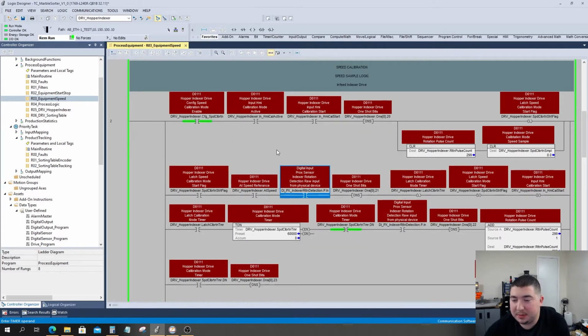So the next thing we want to do is our speed sample. In order to do that, we have to monitor a couple different things all at once. The first thing we're going to do is activate our start flag. So you'll have a calibration mode activation bit on the HMI. This will allow the user to begin the calibration sequence. The calibration mode that we're using is going to require the drive to actually move. So in addition, there's going to be a start push button to actually allow the motor to move. Otherwise, we don't want the motor to just kick on. So the user selects to activate calibration, then they press the start button.